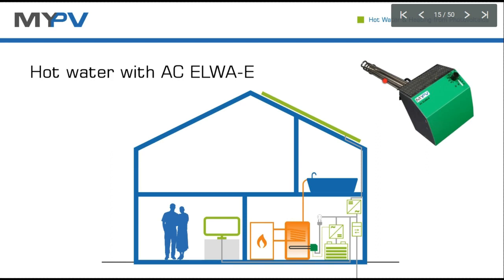The amount of excessive power in a building changes permanently. Not only does PV power change, but loads in the building switch on and off constantly, so the balance at the feeding point changes all the time. The AC-ELWA adjusts its power output accordingly.